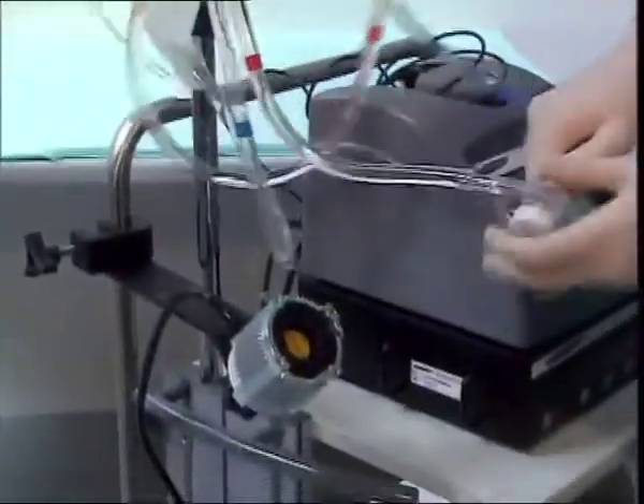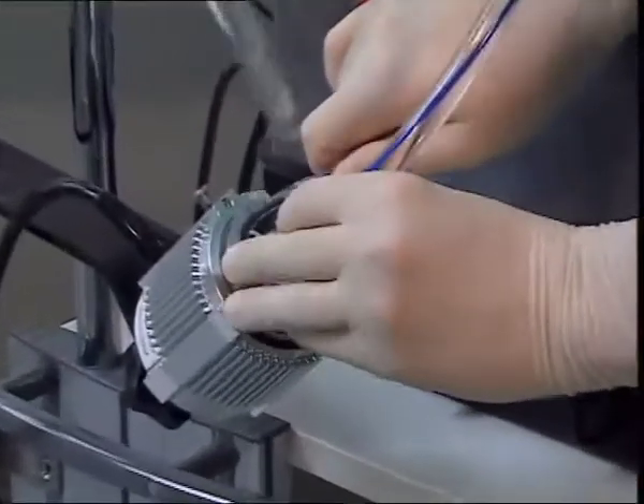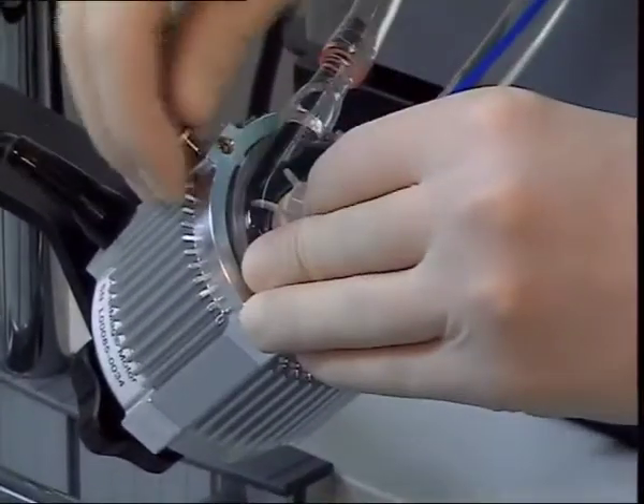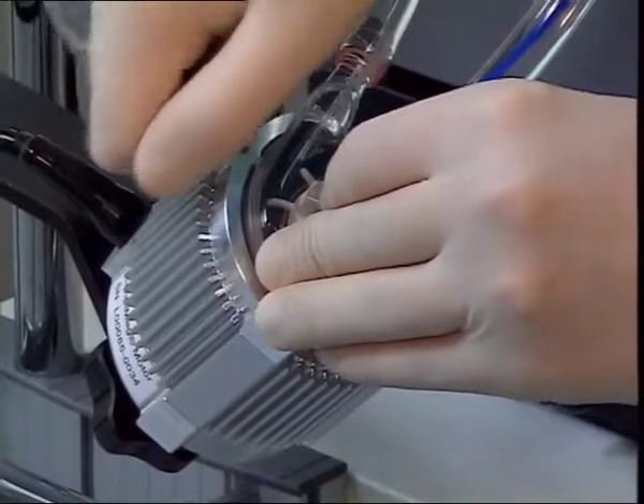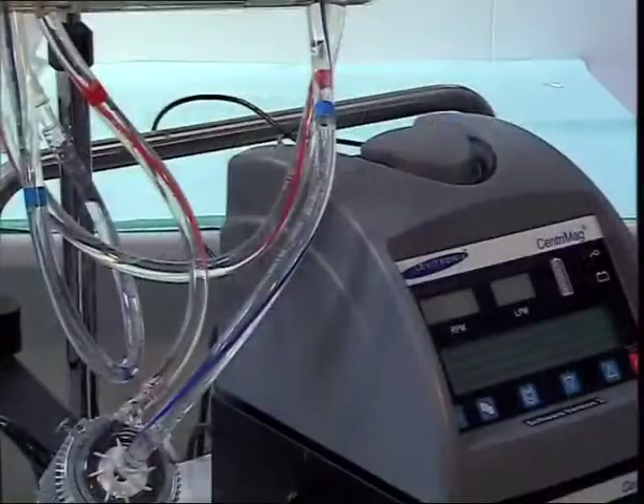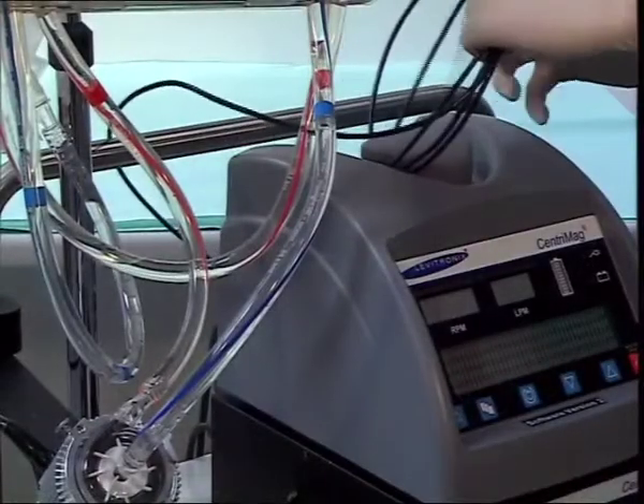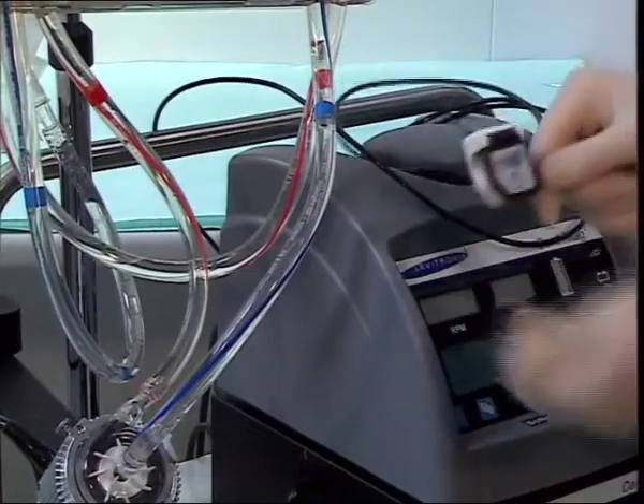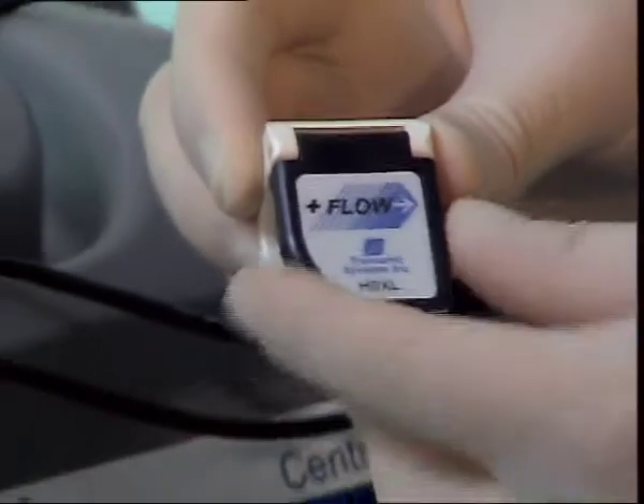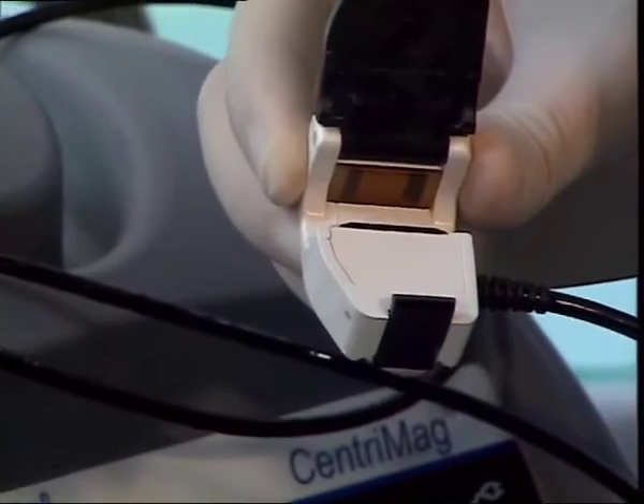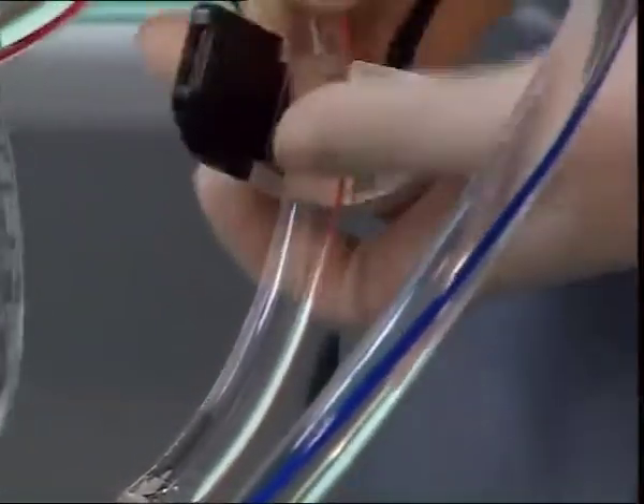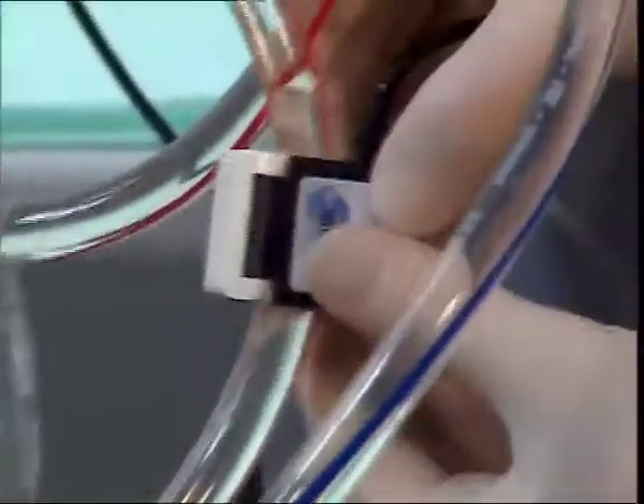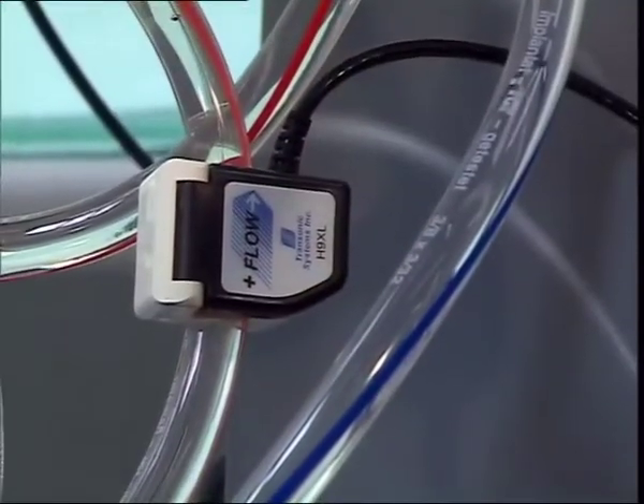Flow is needed to remove small bubbles. The pump is inserted in the head by twisting anti-clockwise and tightening the securing screw. Next, attach the flow probe to the outlet tubing. Depress the black lever and open the gate. Clip the probe onto the tubing, checking carefully for direction of flow marked by the blue arrow.